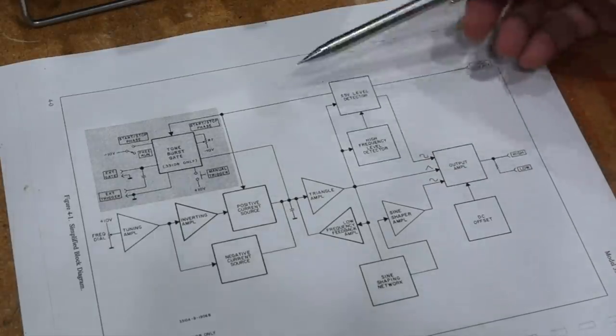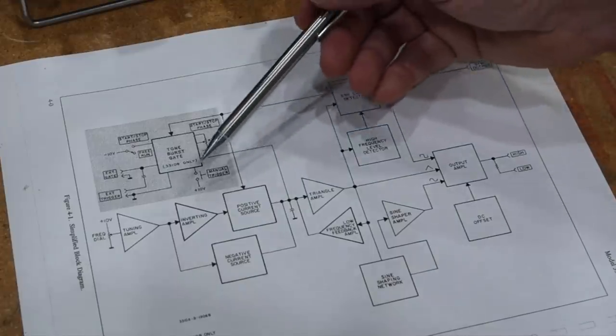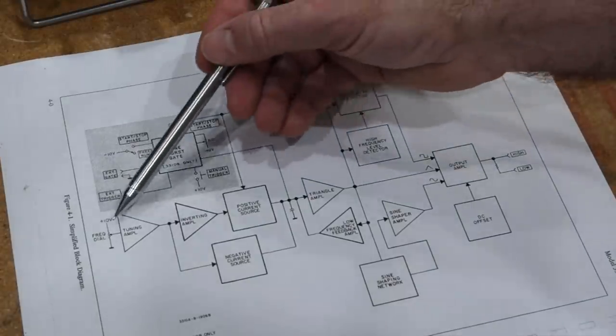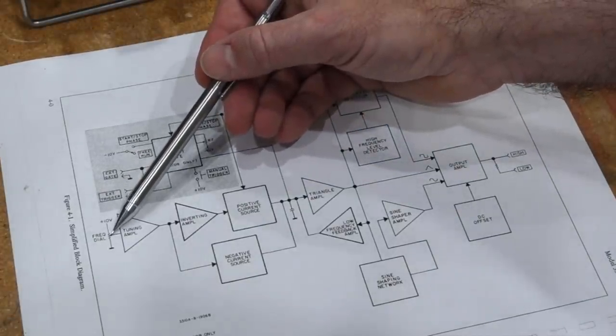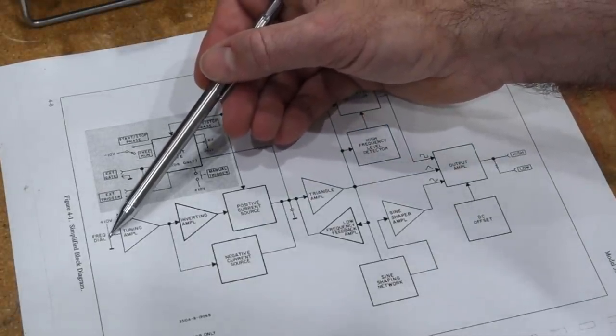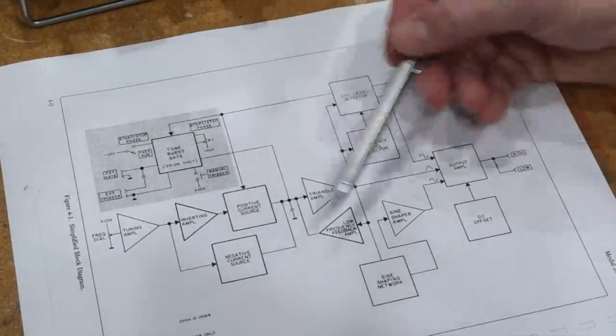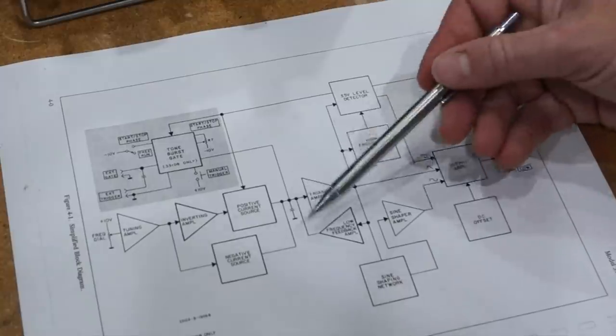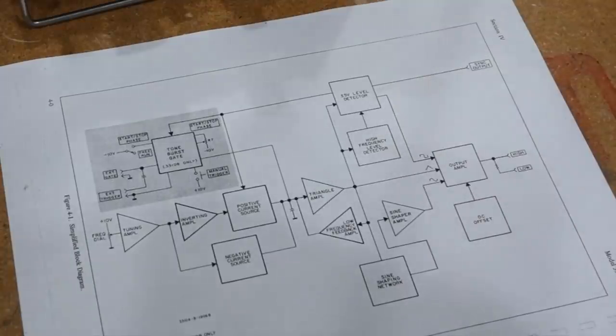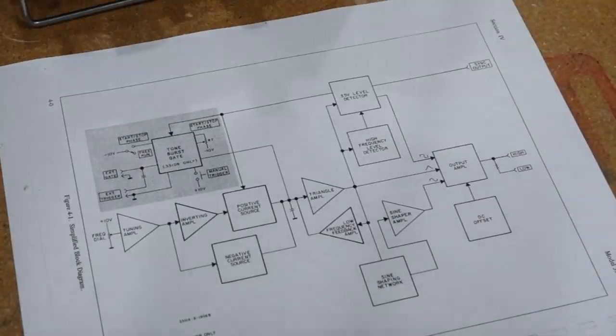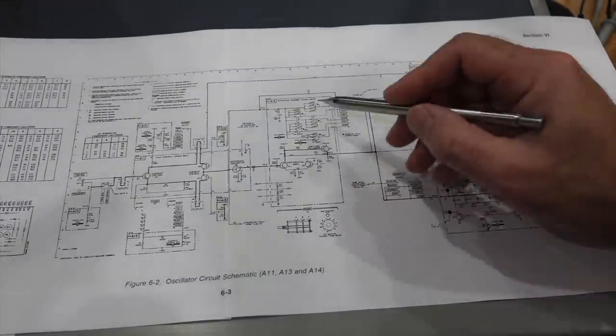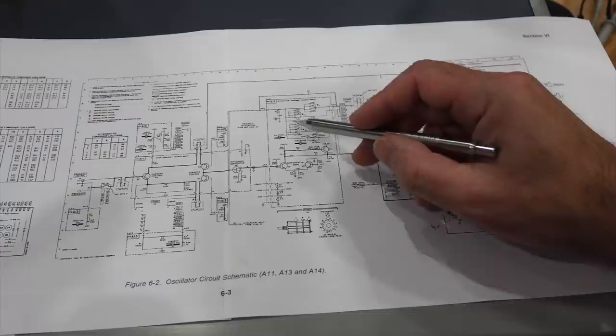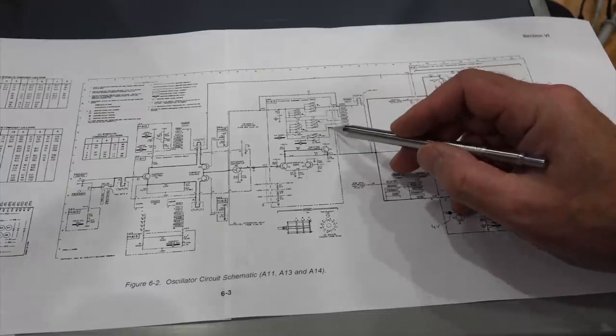So because of this design, you need the positive current source and the negative current source to be exactly matched to give you a symmetrical waveform. This is not tuned properly in my instrument. So the capacitor in question, there are a whole bunch, they are here.